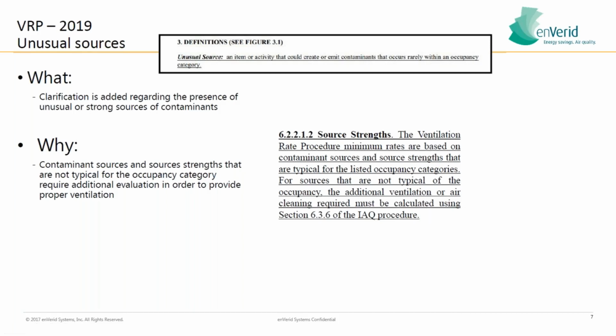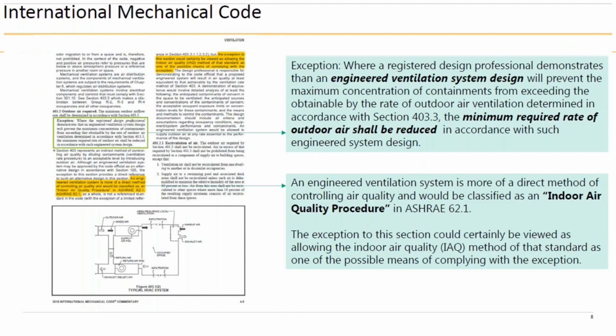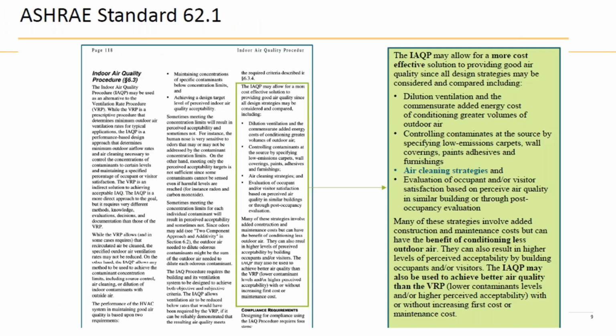ASHRAE 2019 says if you're designing a building that could have nearby unusual sources of contaminants that could create or emit contaminants that occur rarely within an occupancy category, then you must use the indoor air quality procedure. Big changes. So I mentioned that the 62.1 indoor air quality procedure is referenced in the IMC 403. It basically says that the minimum required rate of outdoor air can be reduced with engineered ventilation system design, like an enVerid system, in accordance with the indoor air quality procedure within 62.1. ASHRAE 62.1 itself cites air cleaning strategies as an acceptable and potentially more cost-effective method for providing good indoor air quality.